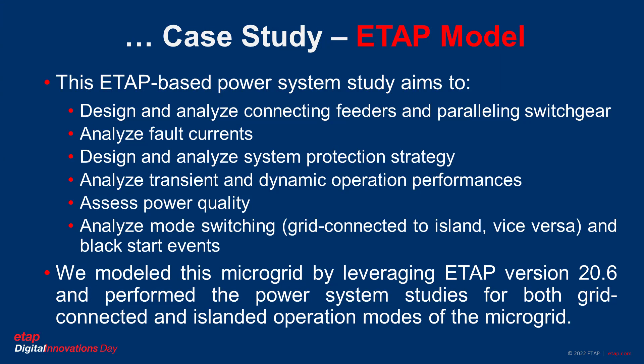The ETAP model of this microgrid system aims to design and analyze connecting feeders, switchgears, and validate their ratings, analyze fault currents, and design the required protection strategy — to analyze different operation performances in both steady-state and transient operation modes, assess power quality including voltage regulation, frequency regulation, and harmonics, and analyze mode switching to verify seamless transfer from grid-connected to island mode and vice versa, as well as black start events.